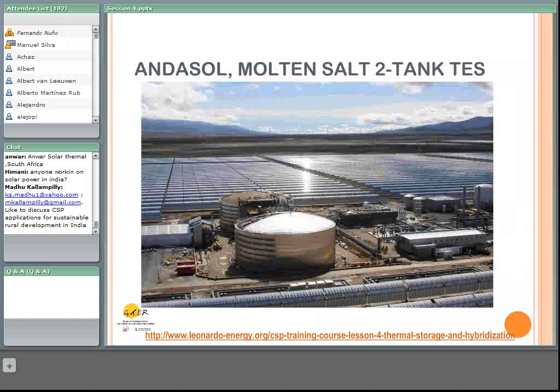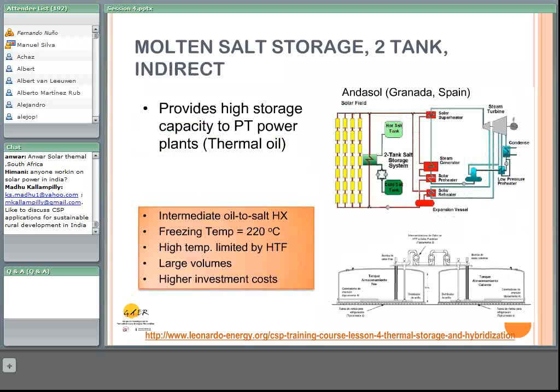As I mentioned, the thermal storage capacity of the Gemasolar plant is roughly the same as the thermal storage capacity of the Andasol thermal storage system, but because the delta T between the hot and the cold tank is more than double that of the Andasol, the volume of salts is approximately 1/3 of that of the Andasol plant. Therefore, the cost per kilowatt hour stored is much less. It's considerably less than that of the Andasol plant.